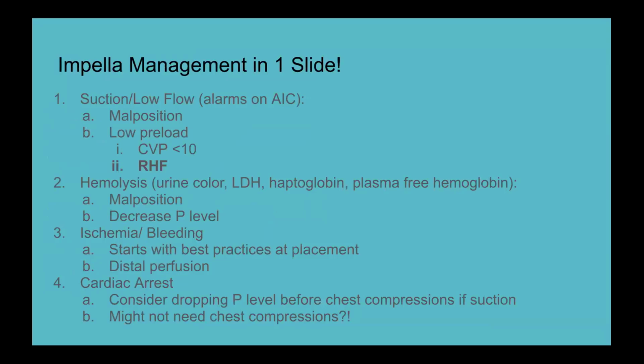So if I could give you one slide of how to manage the Impella, I think the keys would be: the most common issue you're going to have is suction or low flow. These are alarms that you'll see on that automated controller. One of the common things you should rule out is malposition. If the Impella is bumping into the wall of the ventricle, that's going to inhibit it from having any flow. That's easily checked with the AIC as well as with echo.